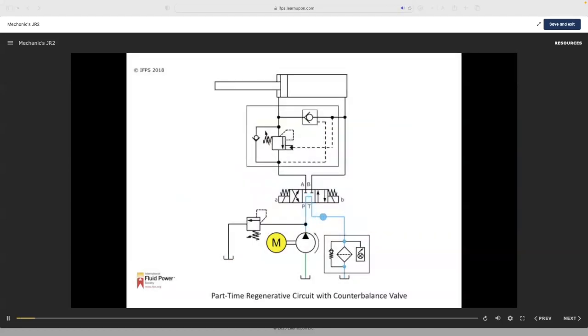Part-time regen circuit at rest. Retract simply sends pump flow through the counterbalance valve bypass check and at the same time holds the pilot-to-close valve closed.